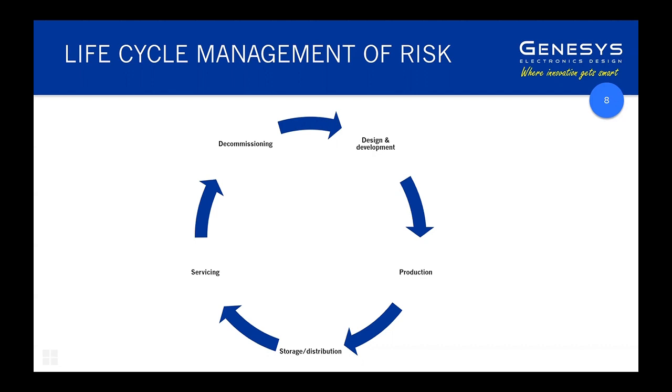They're under document controls. You would expect to do a device characterization, where you go through at the start of the project and ask a series of questions to try and understand the scope of things that you need to consider in the risk management process. For example, is the device implantable? Is it a diagnostic tool? Things around how the product is intended to be used that are relevant and helpful to consider during the process.